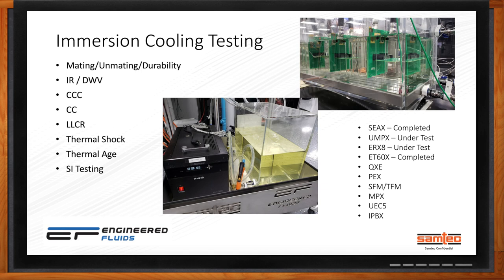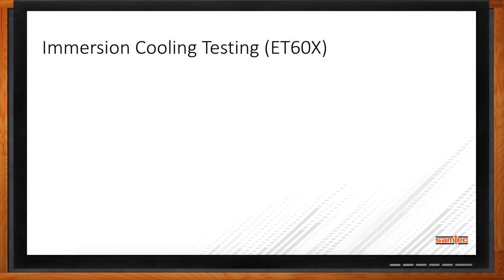We had a lot of learning to do early on — we had to test and retest to make sure thermocouple placement was correct. We were quite shocked at the amount of power we could put through some of our connectors, so we had to upgrade several systems including the cables. In the top right corner you can see our connectors set up in the actual immersion cooling dielectric, where we're testing CCC. The bottom picture shows the cooling tank and pump. Connectors tested or under test include our popular SEAX (completed), the UMPX (currently under test — our micro power system), and the ET60X (completed — our power connector).